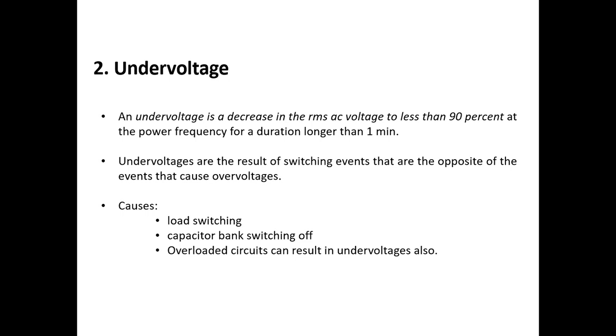Now under voltages. Under voltage means that if the voltage is less than the nominal voltage, we can say it is an under voltage. If it is 90% or less, then also we can say that it is an under voltage. But the duration must be longer than 1 minute, and only then does it come under the under voltage category. Under voltages are a result of switching events that are opposite of the events that cause over voltages. The causes are load switching, switching off capacitor banks, and overloaded circuits can also result in under voltage.